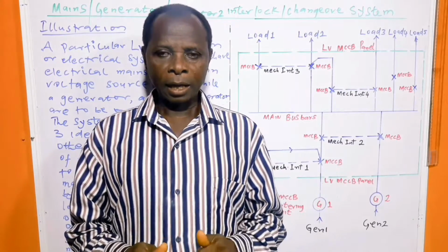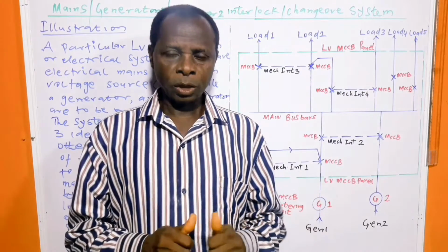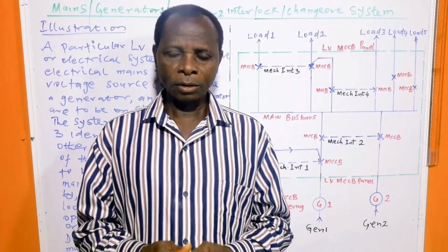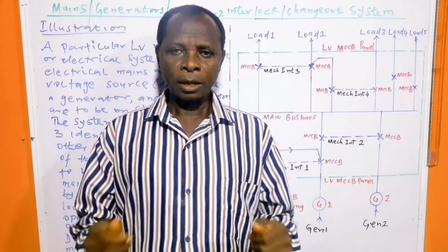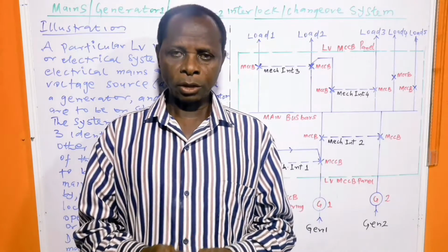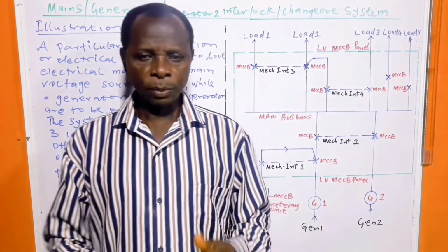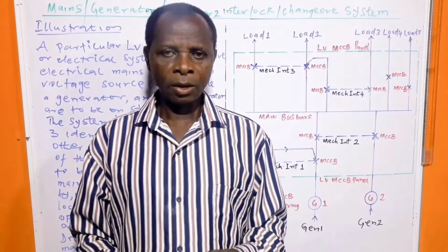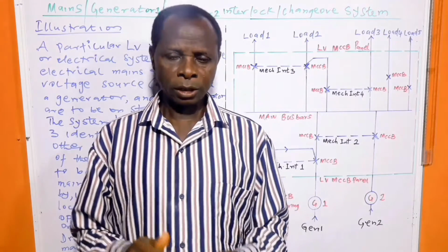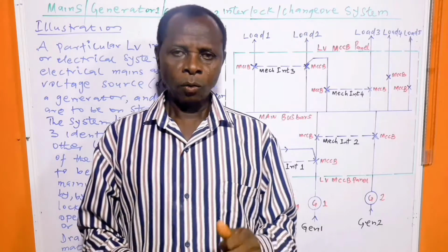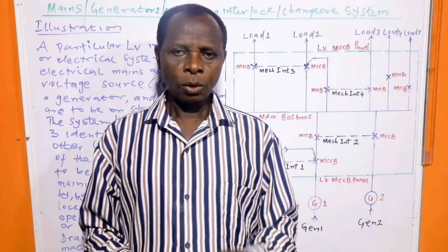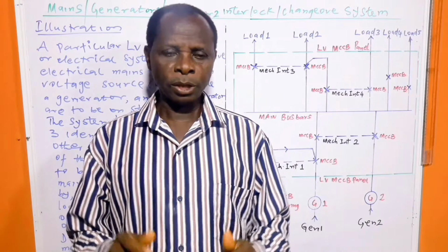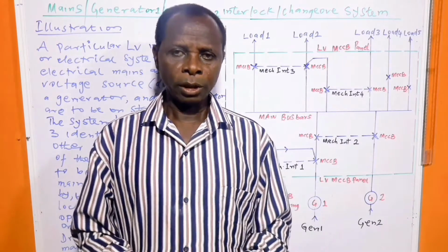The situation will be handled by making use of mechanical interlocks without any operational disconnection or connection. This video is all about mechanical interlock for selecting one out of three voltage sources, and also for selecting one or two of three identical loads without any operational disconnection or connection.